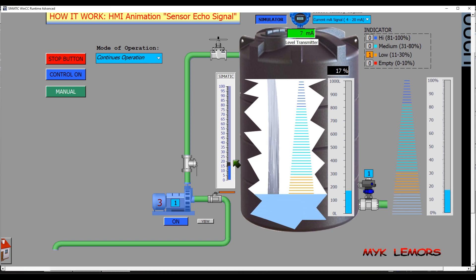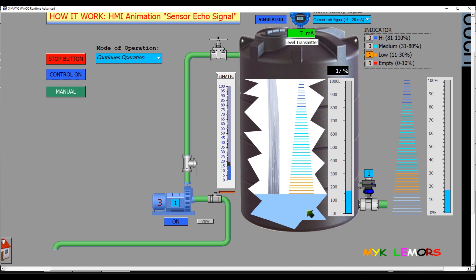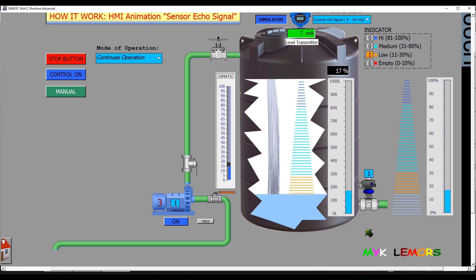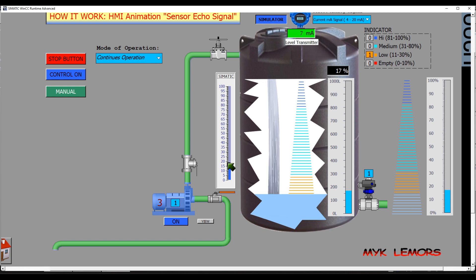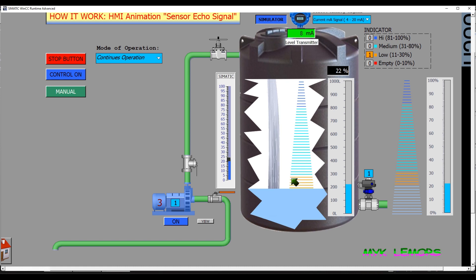When the level increases, the color of the lines changes. The bottom line's color changes to sky blue, matching the color of the water in the tank. When the tank level is 11 to 30%, these lines flash with white and orange colors. The orange color indicates that the tank is at low level.